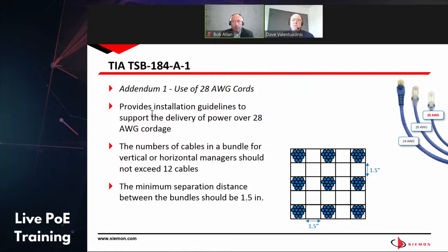There's also a TSB, another technical service bulletin, that talked about the use of 28 gauge cords, the smaller diameter patch cords that have come out in the last couple of years. The only problem is their findings were, to effectively do that, keep your bundle sizes to 12 and keep them an inch and a half apart. I think that's a great engineering practice, but not a great practical practice. If you go into your horizontal and vertical management, it's really not practical to bundle those cables and keep them an inch and a half apart. So I'd say at the very least, if you're doing 28 gauge cords in a PoE application, try to limit your bundle size to at least a group of 12.